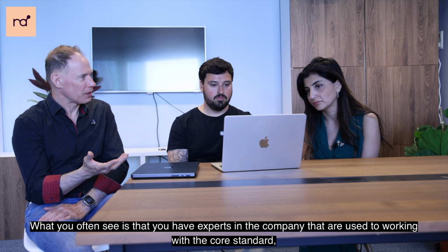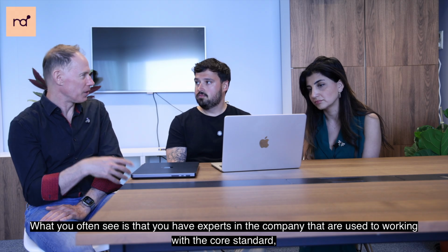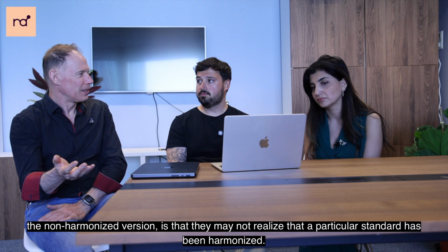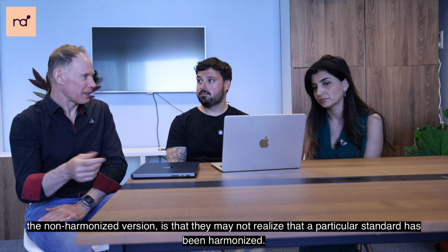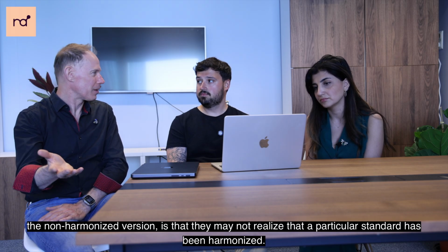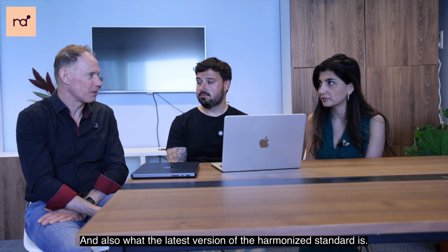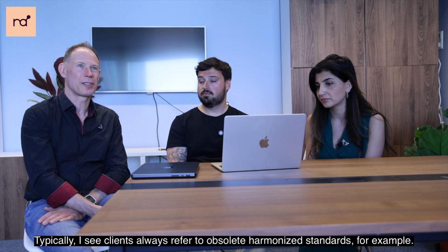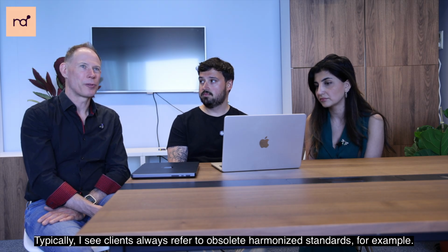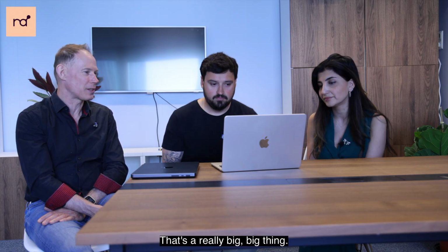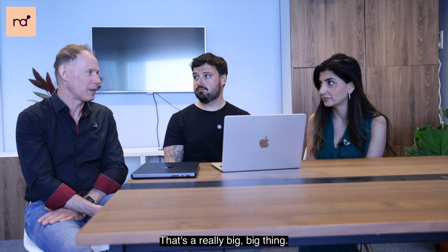What you often see is that you have experts in a company that are used to working with the core standard, the non-harmonized version, and they may not realize that a particular standard has been harmonized. And also what the latest version of the harmonized standard is. Typically, I see clients always refer to obsolete harmonized standards, for example. That's a really big thing.